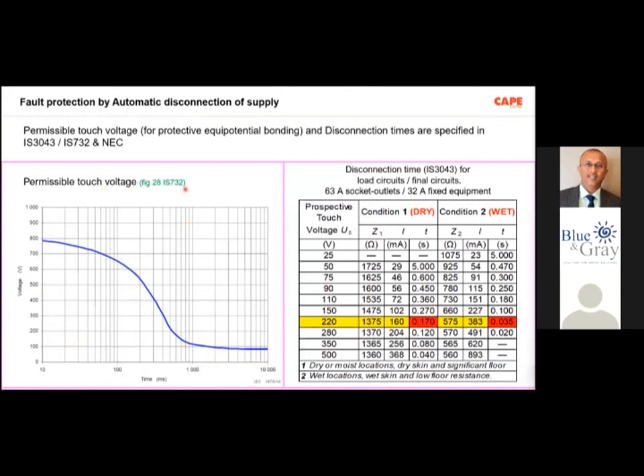Don't cross this voltage. Be it low voltage installation, high voltage installation, or extra high voltage installation, the permissible touch voltage is as per the IEC, and you can see this figure in several standards. I'm showing the figure from IS 732, figure number 28. So this is the maximum permissible touch voltage. What do you do to achieve this permissible touch voltage? You have to make equipotential bonding, which is coming on the next slide.